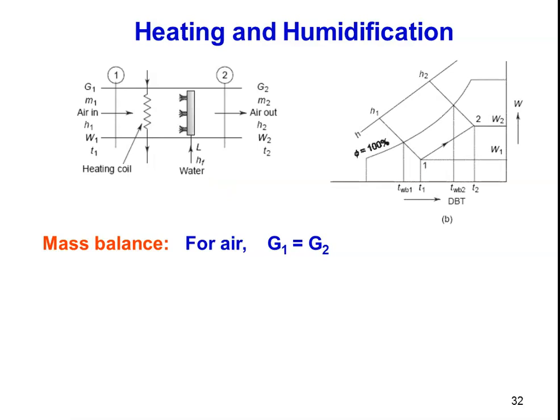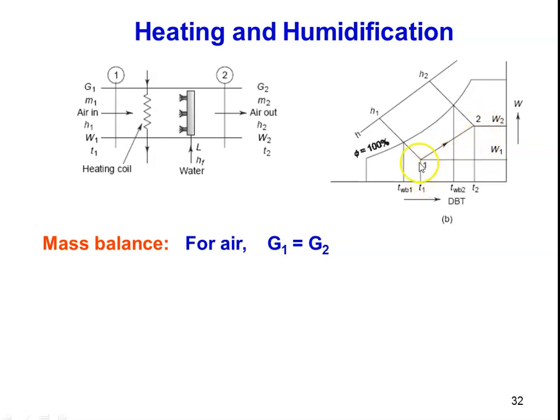Heating and humidification is the opposite of the previous process. At the inlet: G1 (mass of air), M1 (mass of water vapor), H1 (enthalpy), W1 (specific humidity), T1 (temperature). There are two components: a heating coil and a humidifier with a water spray system. Adding water vapor by spraying increases specific humidity. On the psychrometric chart, heating is a horizontal line, humidification is a vertical line, so the combined process from 1 to 2 is an inclined line.